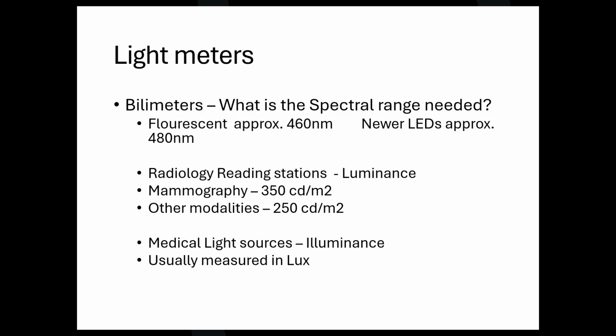So let's talk about luminance and illuminance a second here. Luminance is the amount of light that's emitted by something. Illuminance is the amount of light that is hitting something. There's a difference in it. Okay, go into your radiology area. How many of you know the standard for measuring your radiology reading screens? Yes, there is a standard, and those things should be measured at least annually. So since we're measuring what is radiated, what it is emitting, we have to measure that in luminance, or candela per meter squared is the unit. If we're trying to use something that measures in lux, which is illuminance, no, you're using the wrong device. You are not going to get an accurate number.